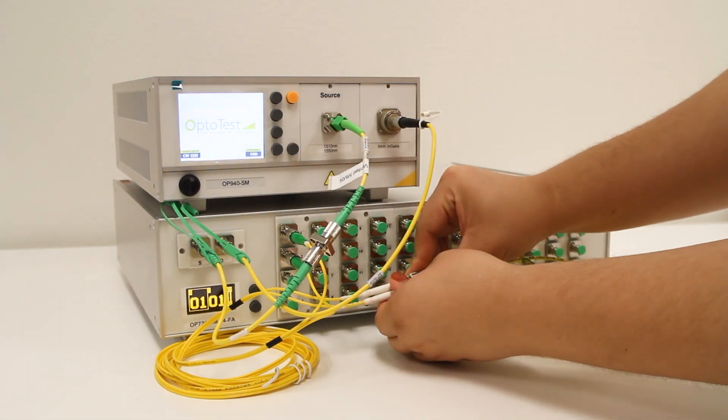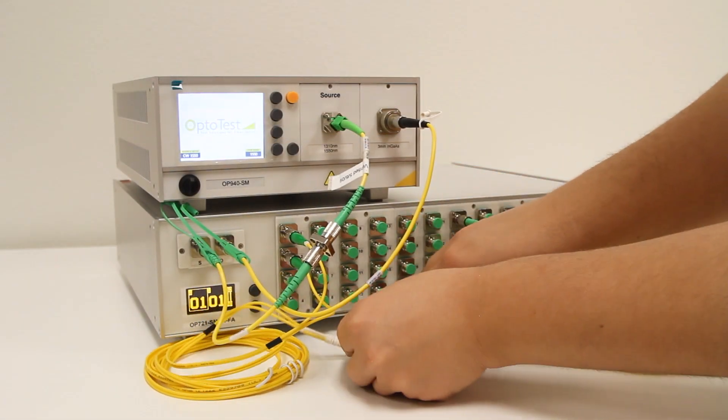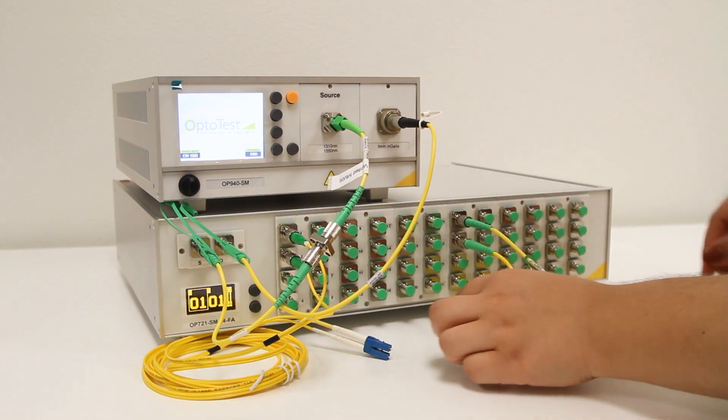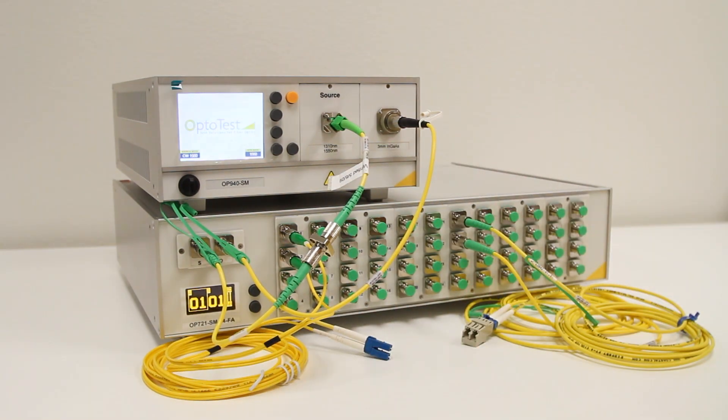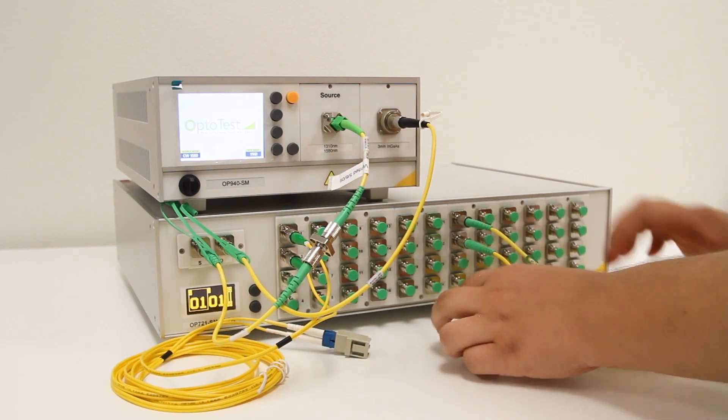Now we disconnect the reference cables from each other before moving on to the return loss reference. This ensures that we reference to flat polish connectors that are open to air.